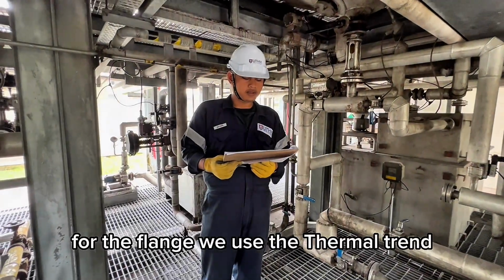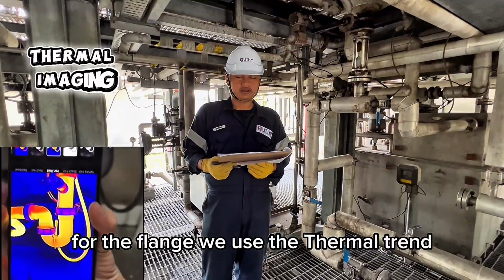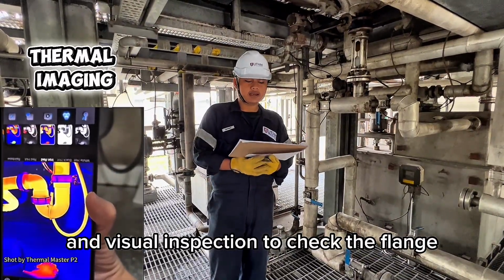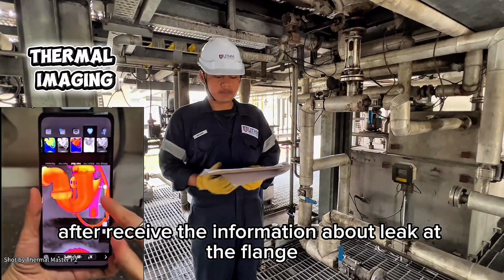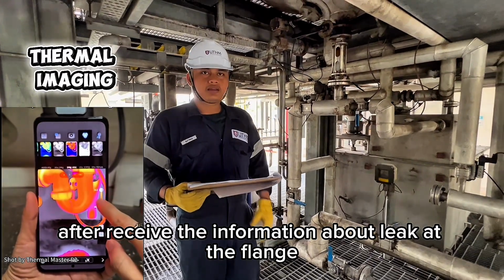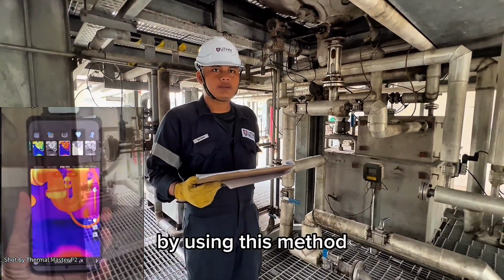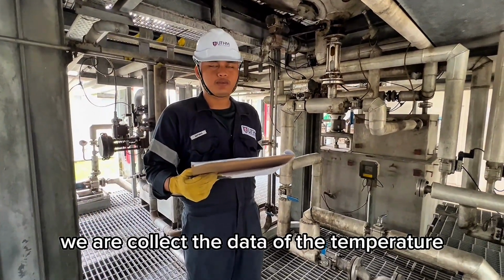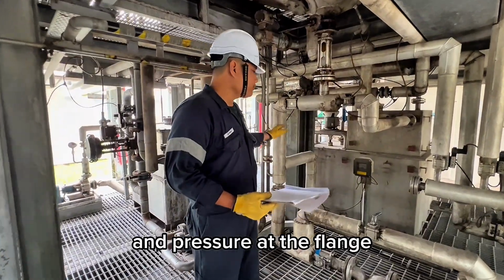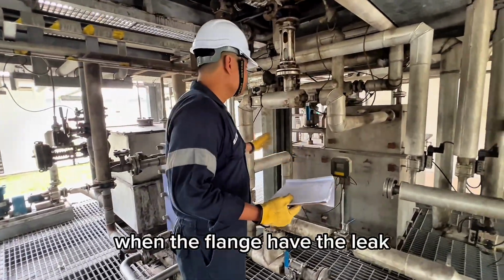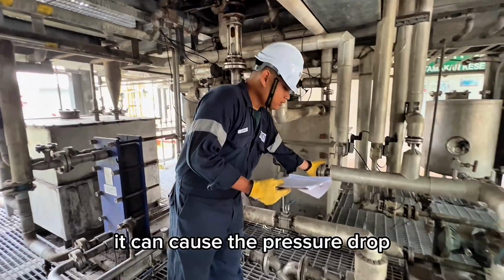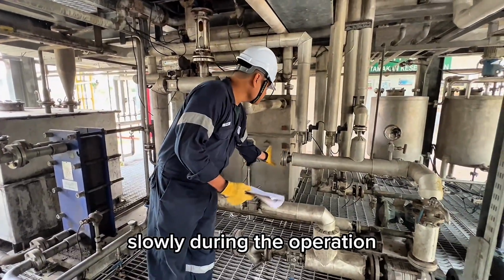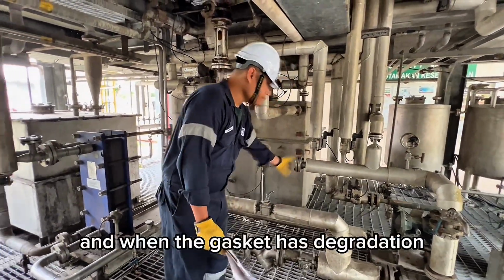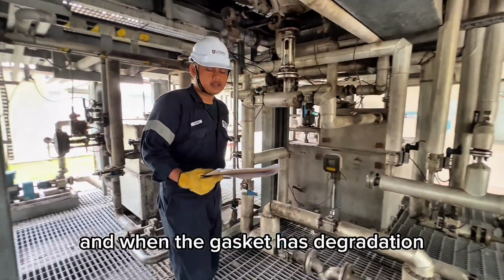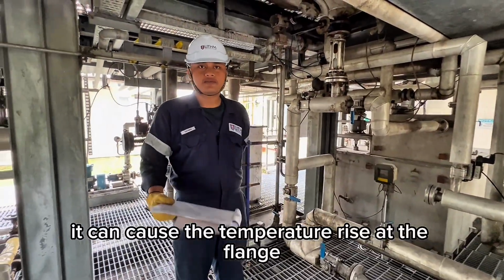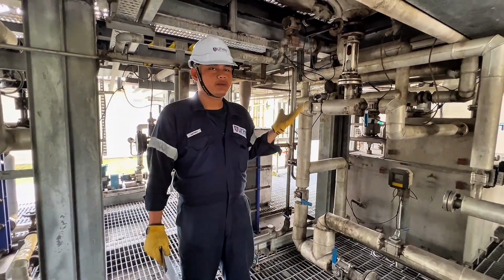For the flange, we use thermal trend and visual inspection to check the flange after receiving information about a leak at the flange. By using this method, we collect the data of the temperature and pressure at the flange. When the flange has a leak, it can cause the pressure to drop slowly during operation. And when the gasket has degradation, it can cause the temperature to rise at the flange.